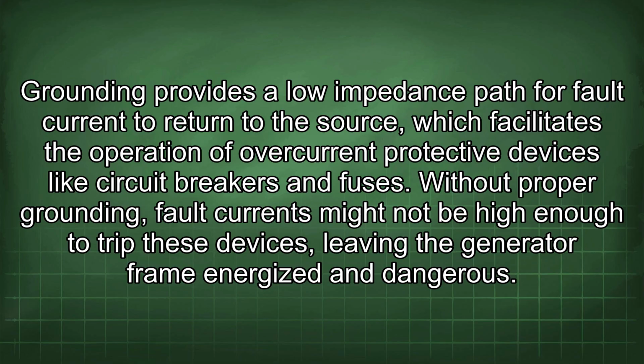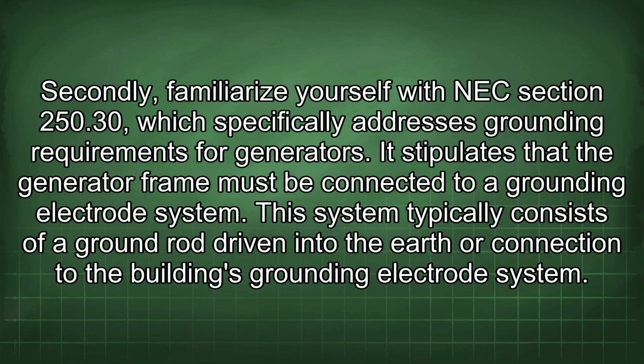Grounding provides a low impedance path for fault current to return to the source, which facilitates the operation of overcurrent protective devices like circuit breakers and fuses. Without proper grounding, fault currents might not be high enough to trip these devices, leaving the generator frame energized and dangerous. Secondly, familiarize yourself with NEC section 250.30, which specifically addresses grounding requirements for generators.